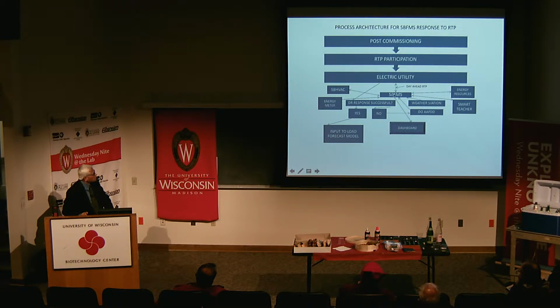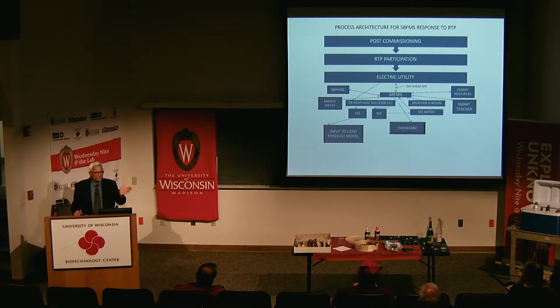Remember, I told you before that you can set up the control strategies as a function of outdoor temperature. The weather station here sends the weather data forecast 1 day ahead of time. And again, you have got smart teacher, which I discussed before. So once you have weather data 1 day ahead of time, and from commissioning you have all the control strategies, the smart building facility management system can automatically trigger what control strategy should come at what time.